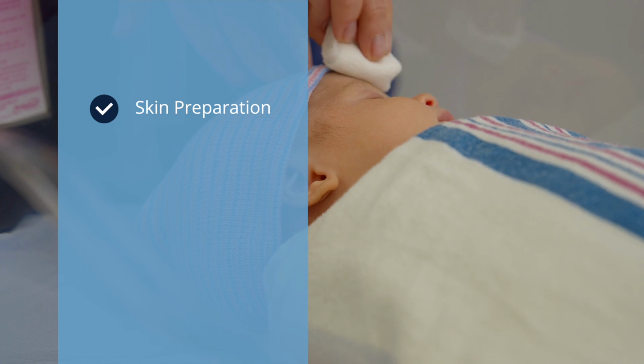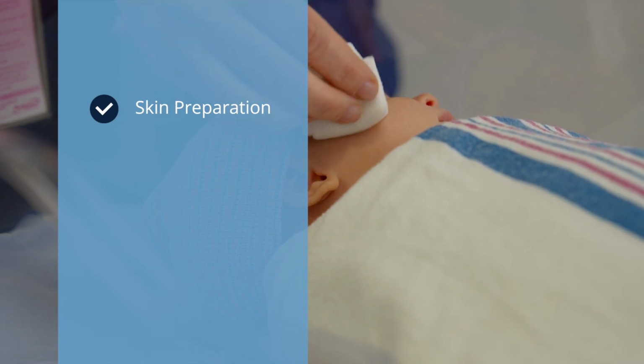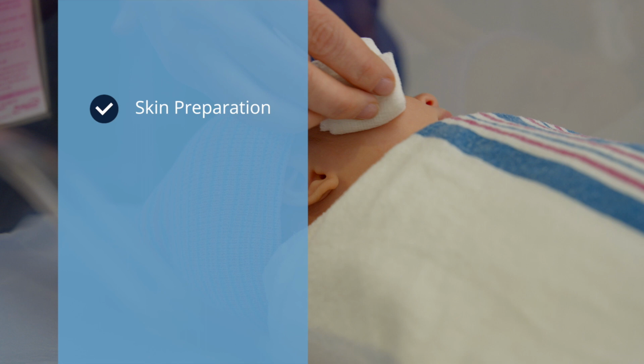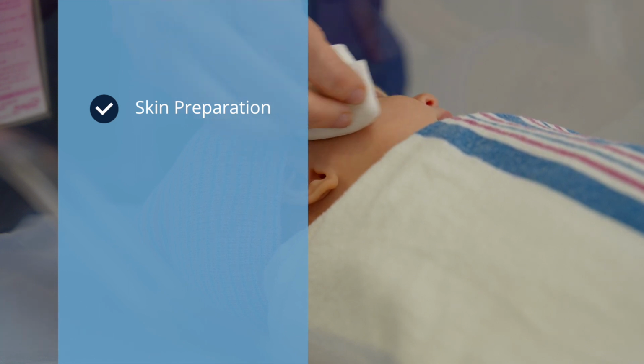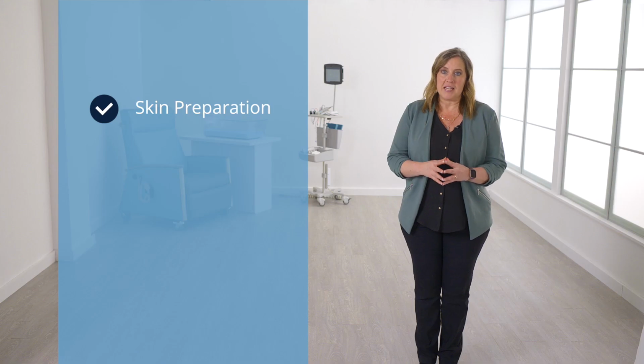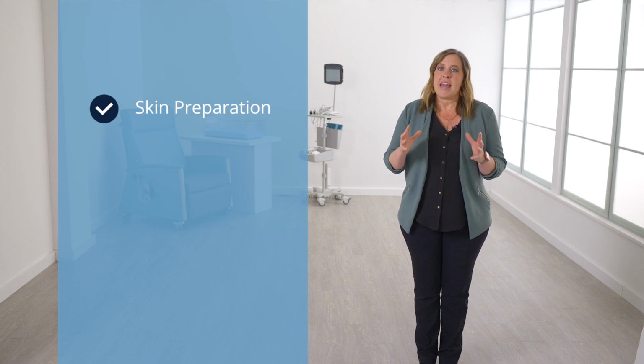Using NuPrep on a gauze pad and rubbing briskly at each electrode site will ensure low impedance. If you perform the impedance test and any impedance is above 10 kiloohms, stop the test, re-prep the skin. I cannot stress enough how much of an impact this will have on your infant testing.